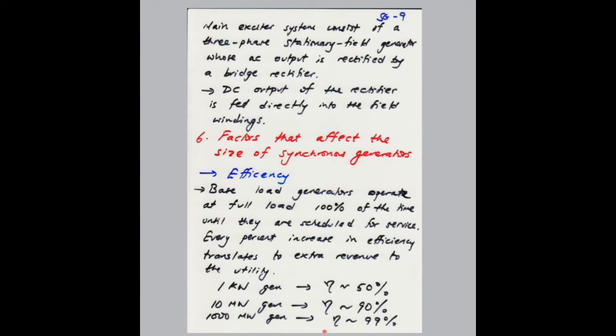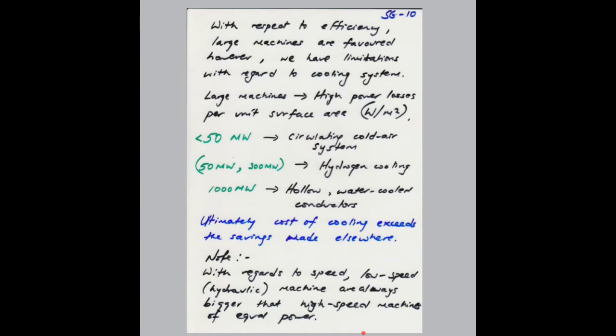So now, if you look at how when the size of the generator is changing, you will see that there is a major change in the efficiency. From 1 kilowatt, you're getting efficiency of around 50%. And if it's a larger machine, which is 1,000 megawatt, you're getting an efficiency which is close to 99%. So with respect to efficiency, obviously larger machines are favored as compared to lower size machines. However, we encounter limitations with regards to the cooling system when we use large machines. So large machines have high power losses per unit surface area, so that's in watt per meter squared.